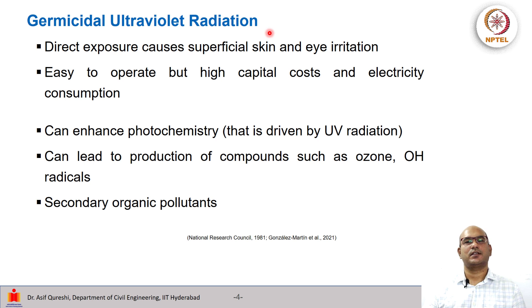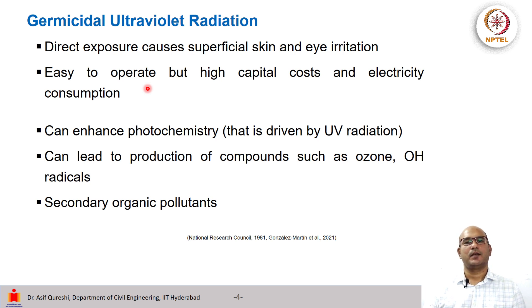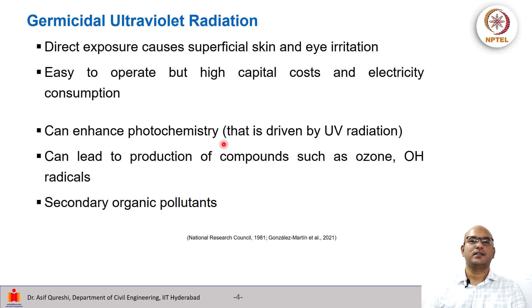The issues with germicidal UV radiation lamps are that direct exposure to humans may cause skin and eye irritation. These lamps are easy to operate since all we need to do is turn on the light, but they have high capital cost and sometimes high electricity consumption. Another issue is that UV lamps can enhance indoor air photochemistry — reactions driven by UV radiation — which can lead to production of ozone and hydroxyl radicals, which can produce secondary organic pollutants.